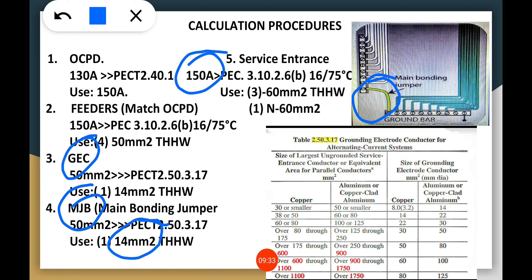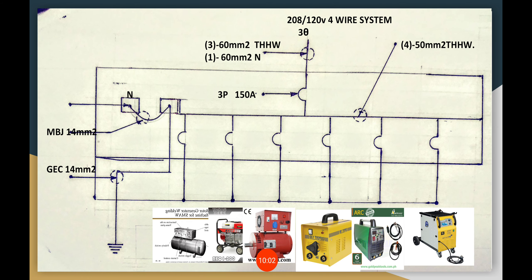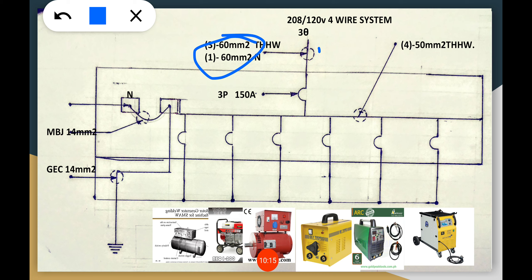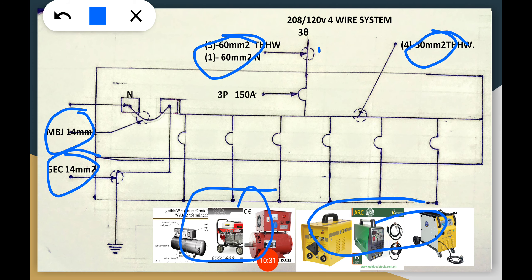For the service entrance, we use the 150-ampere rating and go to Table 310.2.6b16 at 75 degrees — 75 degrees because it is over 100 amps. With a full neutral, the neutral is 60 mm² THHW, the same size as the phase conductors at 60 mm² THHW. Summary: supply is 208/120V 3-phase system, with 3 × 60 mm² THHW for service entrance, 4 × 50 mm² THHW for the feeder, MBJ at 14 mm², GEC at 14 mm², serving a group of motorized and non-motorized welding machines.